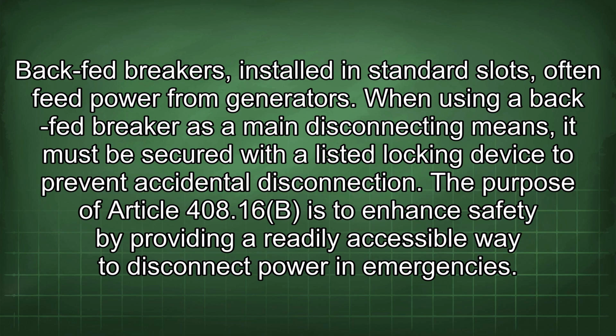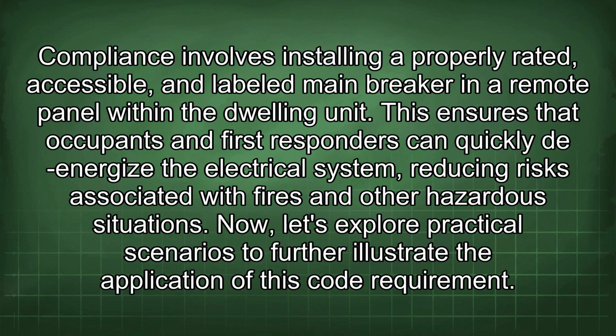When using a backfed breaker as a main disconnecting means, it must be secured with a listed locking device to prevent accidental disconnection. The purpose of Article 408.16(B) is to enhance safety by providing a readily accessible way to disconnect power in emergencies. Compliance involves installing a properly rated, accessible, labeled main breaker in a remote panel within the dwelling unit.